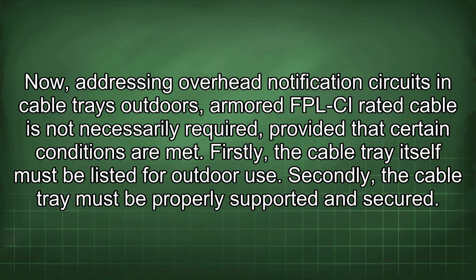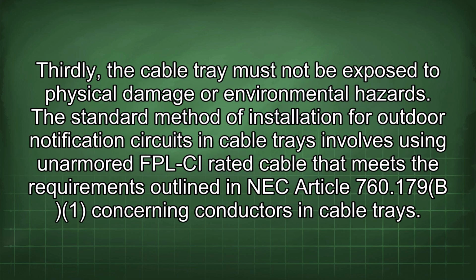Now, addressing overhead notification circuits in cable trays outdoors, armored FPL-CI rated cable is not necessarily required, provided that certain conditions are met. Firstly, the cable tray itself must be listed for outdoor use. Secondly, the cable tray must be properly supported and secured. Thirdly, the cable tray must not be exposed to physical damage or environmental hazards.